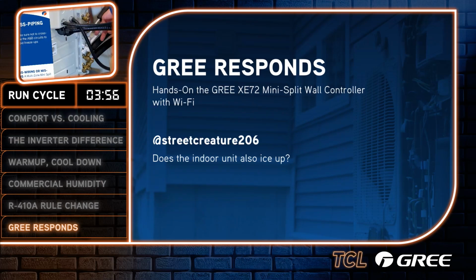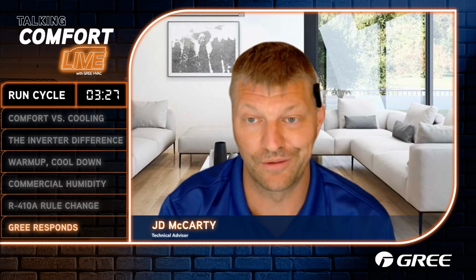All right, let's see here. We have another question. So this question was, does the indoor unit also ice up? And it's basically he was troubleshooting a cross-wired or mispiped multi-zone mini split. So to answer his question, yes, depending on if you're in cooling mode and we're sending refrigerant to the wrong head, it will ice up. That's sometimes exactly how we know we have an issue.